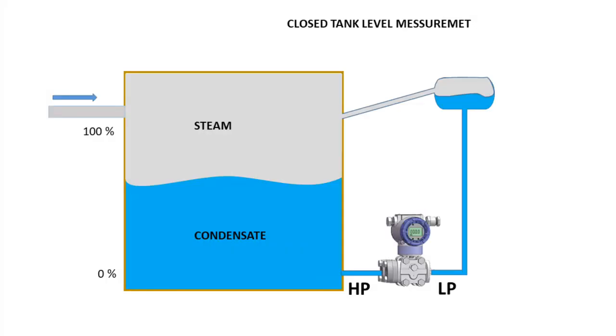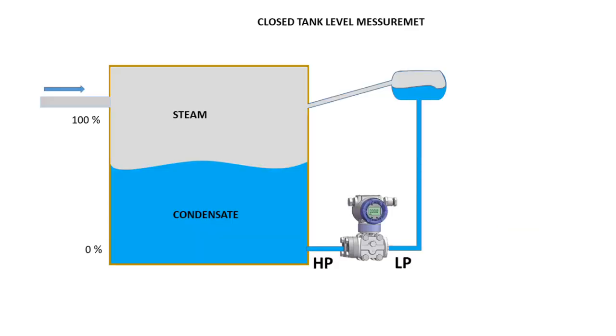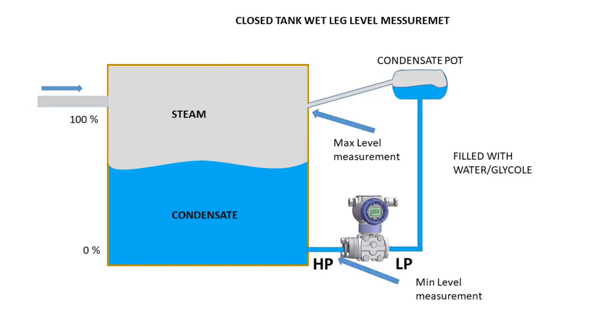Today we are going to discuss DP level measurement using the wet leg method. In the previous lesson we learned about the dry leg type installation. In dry leg, the low side impulse is filled with air from the top of the tank. In the wet leg method, the low side impulse line will be filled with water or glycol, because when we measure the level of a process which has the property of condensate, it will condensate into the impulse line and cause error in the measurement. For example, steam.